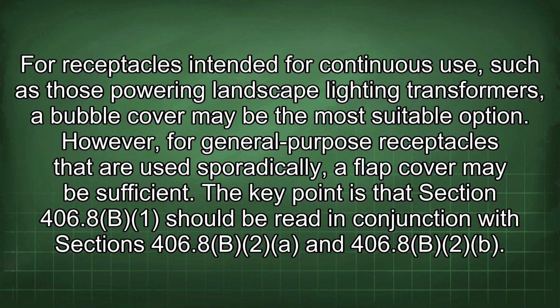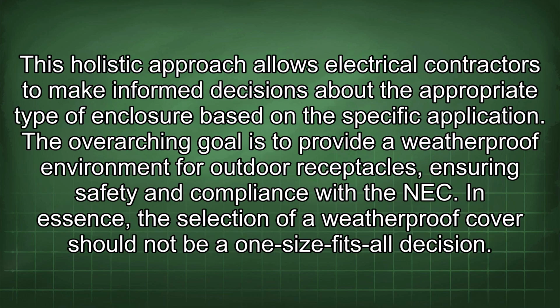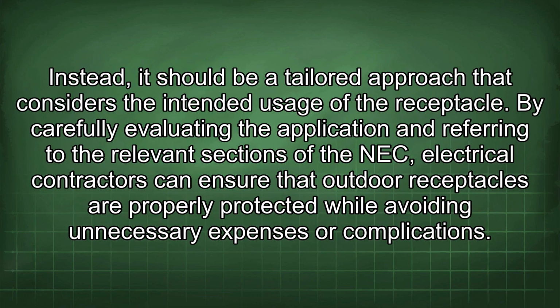The key point is that Section 406.8(B)(1) should be read in conjunction with Sections 406.8(B)(2)(a) and 406.8(B)(2)(b). This holistic approach allows electrical contractors to make informed decisions about the appropriate type of enclosure based on the specific application. The overarching goal is to provide a weatherproof environment for outdoor receptacles, ensuring safety and compliance with the NEC. In essence, the selection of a weatherproof cover should not be a one-size-fits-all decision. Instead, it should be a tailored approach that considers the intended usage of the receptacle. By carefully evaluating the application and referring to the relevant sections of the NEC, electrical contractors can ensure that outdoor receptacles are properly protected while avoiding unnecessary expenses or complications.